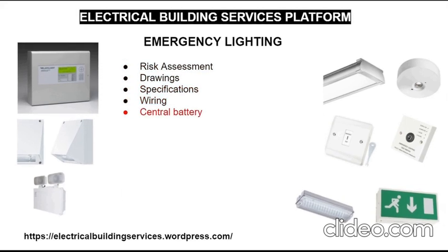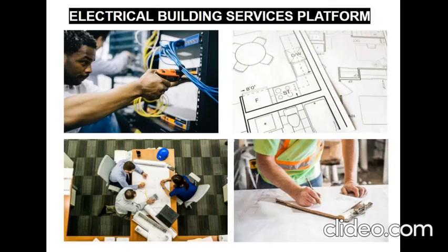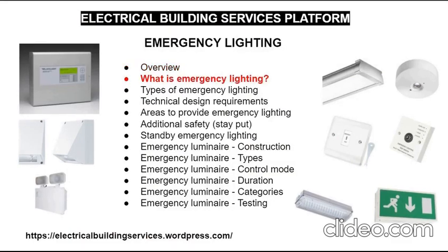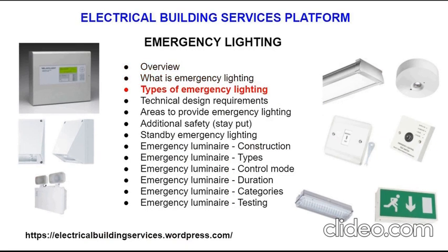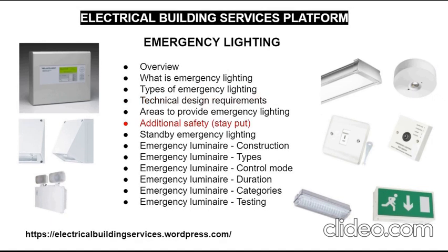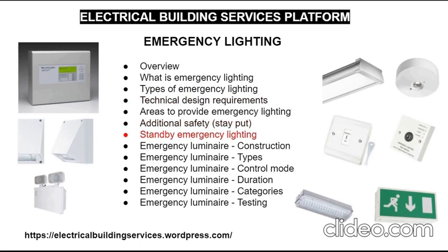Industrial building, public exit, doors. You must have an emergency luminaire installed near exit doors, non-residential. You need 1 hour. A multi-story dwelling over 10 stories, you need 3 hours. Residential, special care, sleeping risk, 3 hours.